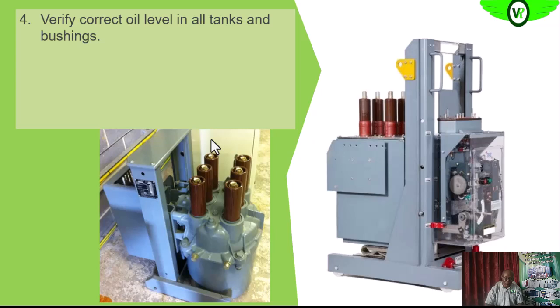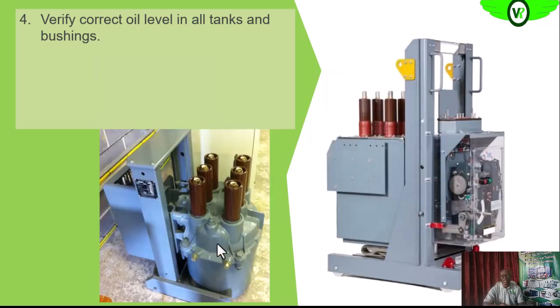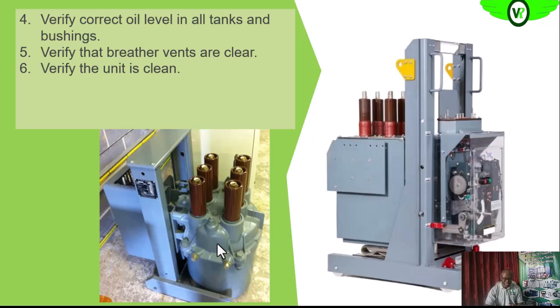Then the oil level in the tank, we want to be sure we have the appropriate oil level. If it is short, we'll top it up with the recommended oil. If there are bushings, and if the bushings are also filled with insulating oil, we want to check that the oil is at the appropriate level. If there are breathers too, we also want to see that the vents are clear. Those are part of the physical inspection we are to carry out.